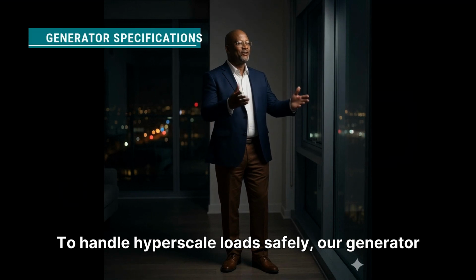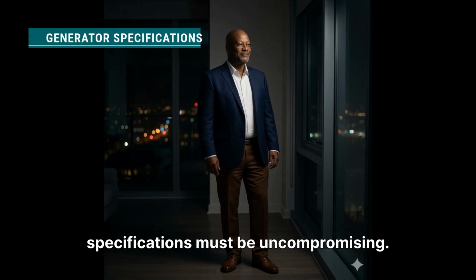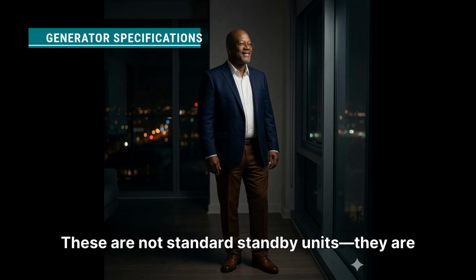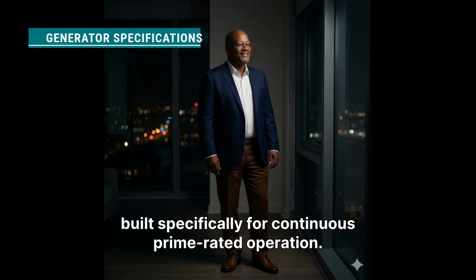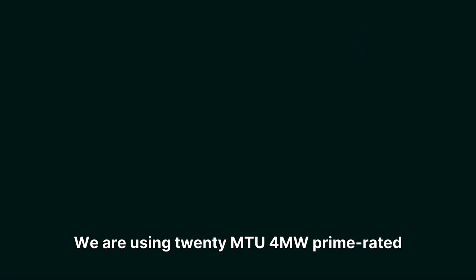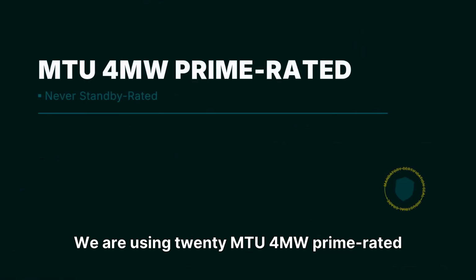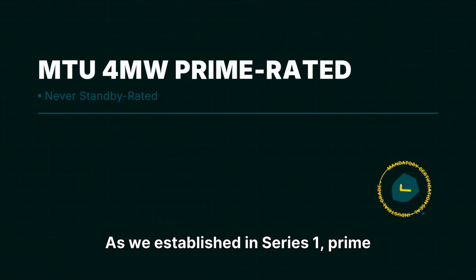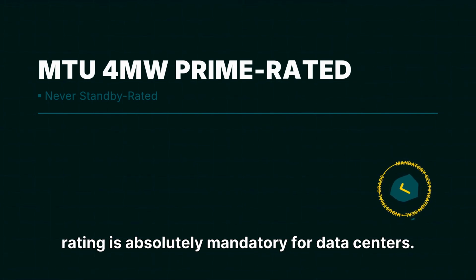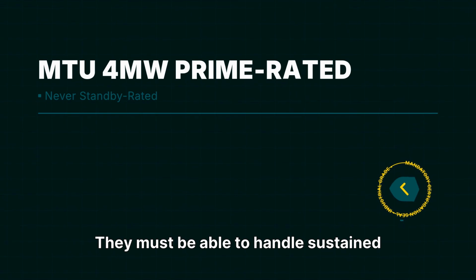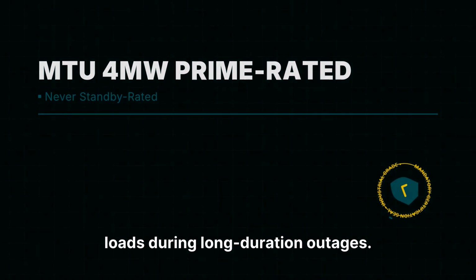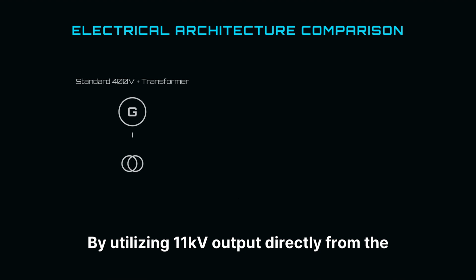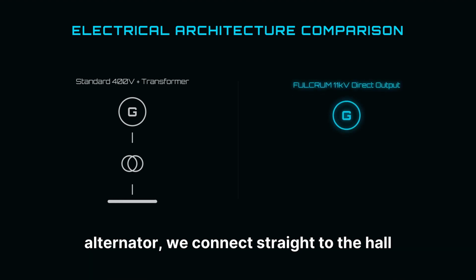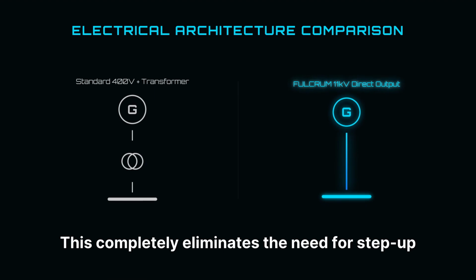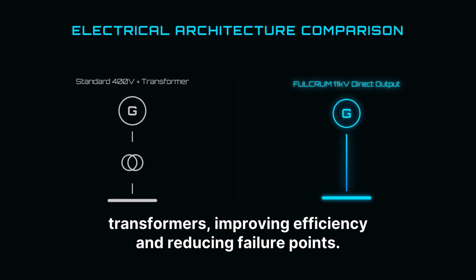To handle hyperscale loads safely, our generator specifications must be uncompromising. These are not standard standby units. They are built specifically for continuous prime-rated operation. We are using 20 MTU 4MW prime-rated generators. As we established in Series 1, prime rating is absolutely mandatory for data centers. They must be able to handle sustained loads during long-duration outages. By utilizing 11 kV output directly from the alternator, we connect straight to the hall distribution busbar. This completely eliminates the need for step-up transformers, improving efficiency and reducing failure points.